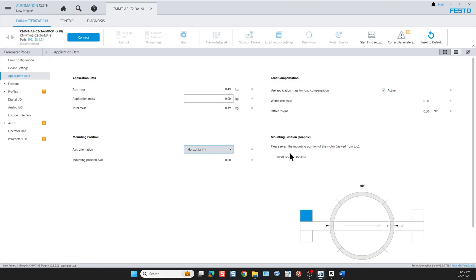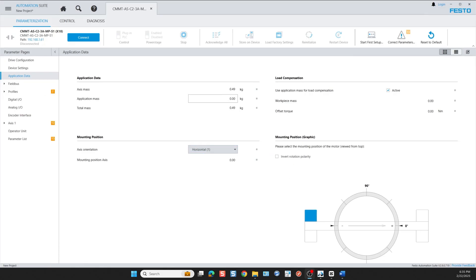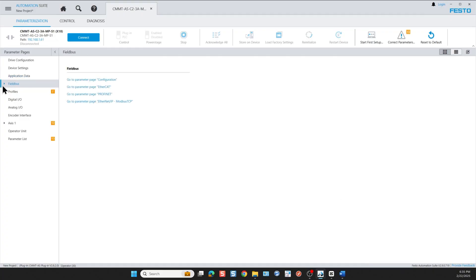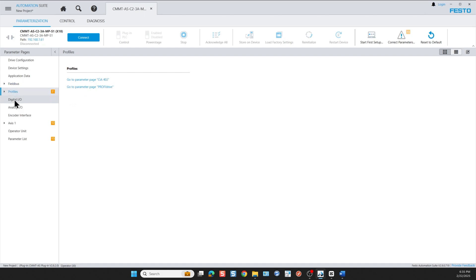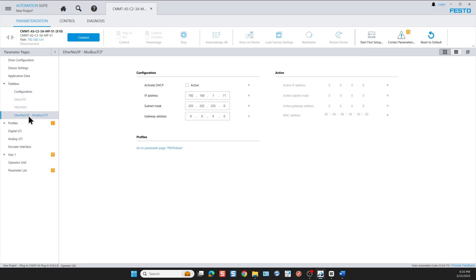You could change the rotation polarity by clicking here or here. The next entry we need to change is very important. It is the fieldbus configuration. The available protocols are Profinet and EtherCAT, but in this case we're using Ethernet/IP. We click on Ethernet/IP and here we can go and change the IP address of the Ethernet control port on the top of the drive, X19 for CMMT-AS drives or XF1 for the CMMT-ST drives.